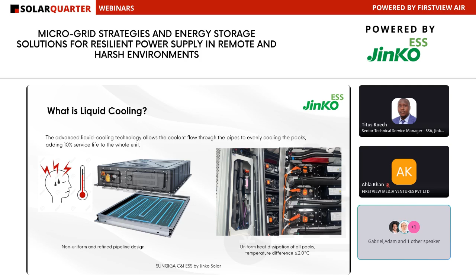For the battery system, the main components are the batteries, the battery packs, which can be either 5 or 8 units. Each battery pack is 43 kilowatt hours, so 5 packs gives 215 kWh, and 8 packs gives 344 kWh. They're all connected in series, with the final termination on the high voltage box.